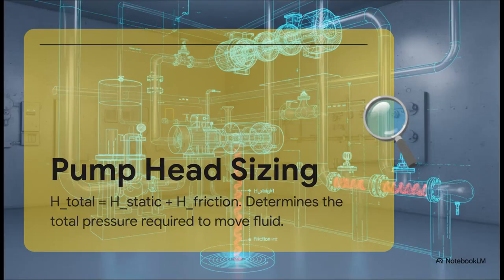Second, pumps. It doesn't matter if it's for water supply or fire protection, you have to know how to calculate the total head. It's the static height you're pumping against, plus all the friction you lose along the way in the pipes. Get this right, and you prove you can size a pump for any system, period.